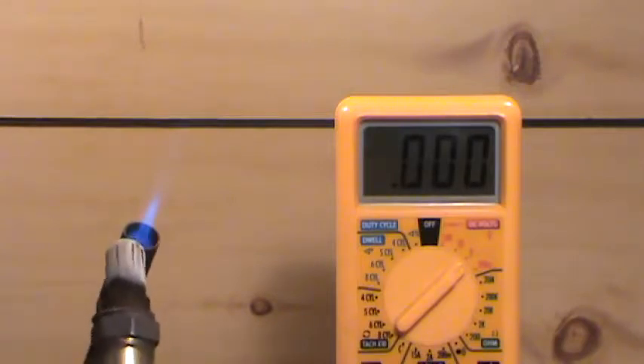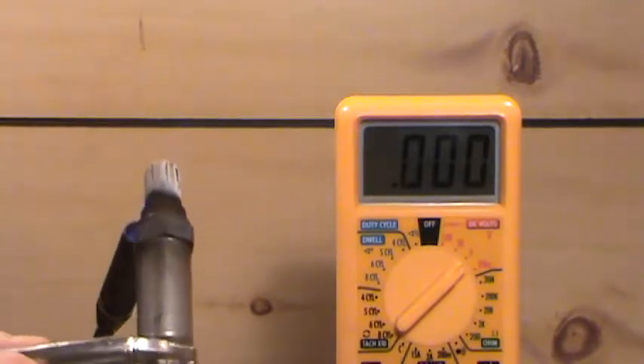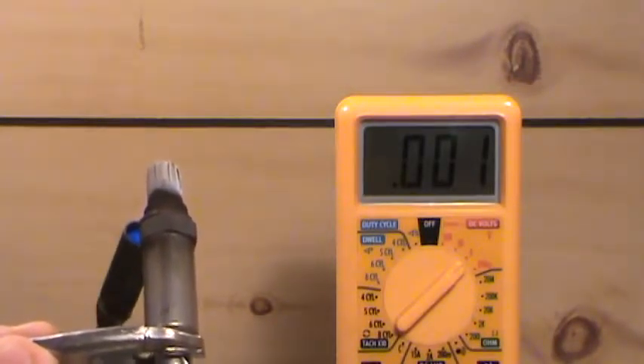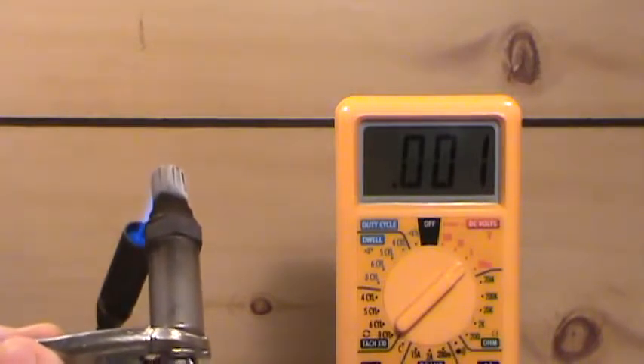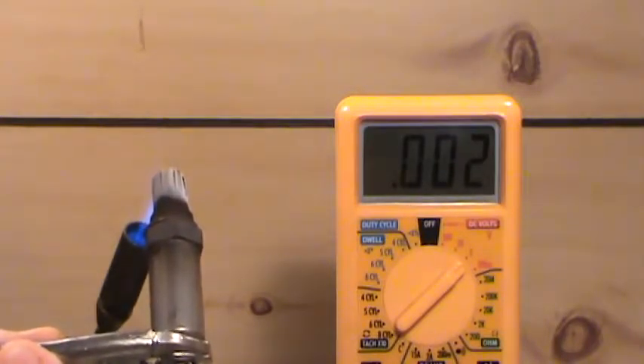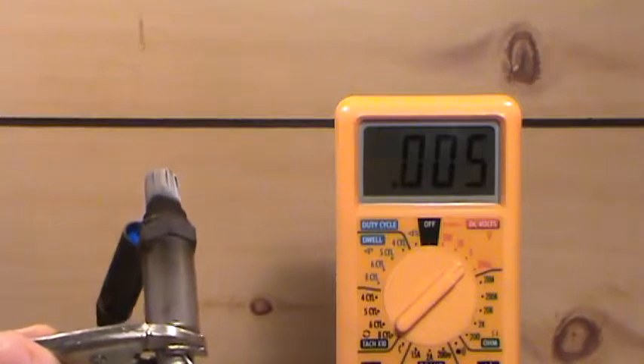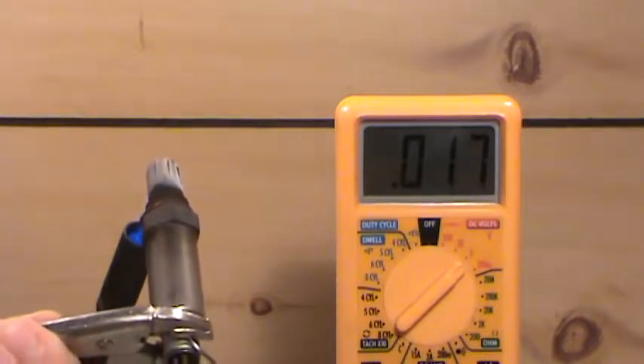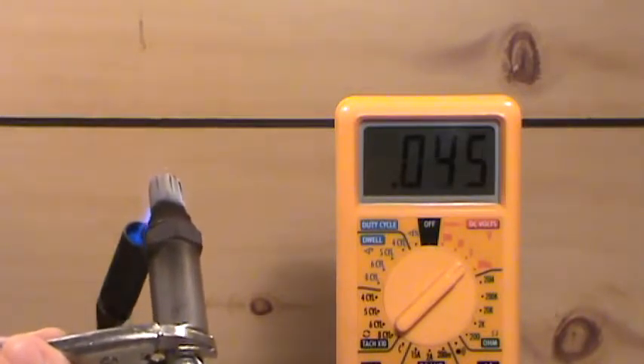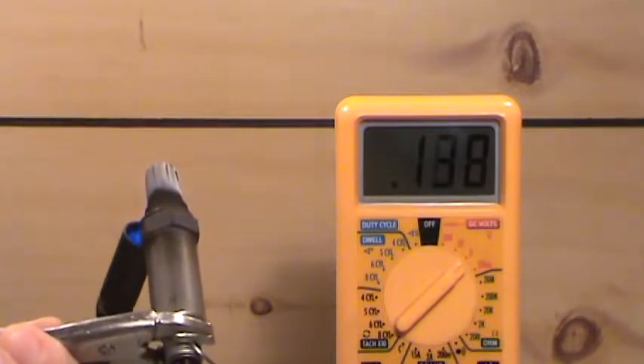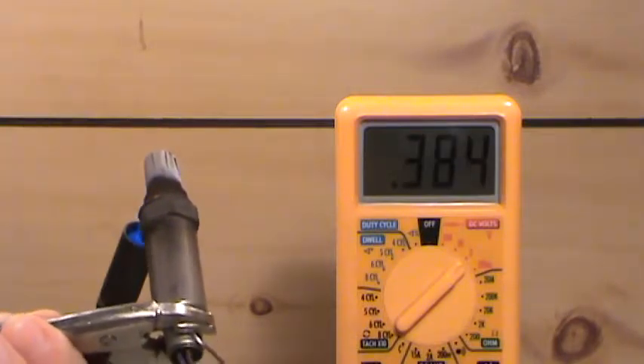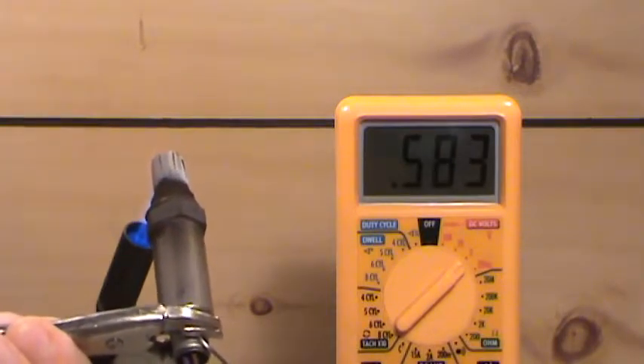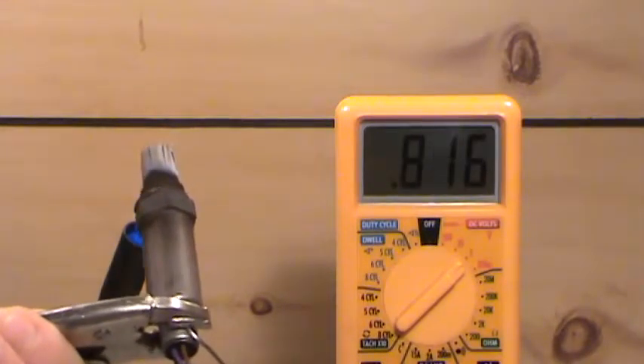Keep your eye on the meter as we heat this thing up. Okay, things are getting pretty hot. Propane burns pretty clean, so I can't really see a whole lot of oxygen in this stream of flame. I'll take the oxygen sensor slightly away from the tip of the flame so we can maybe get it to drag some more oxygen in there, and we'll watch it as we move this thing around.